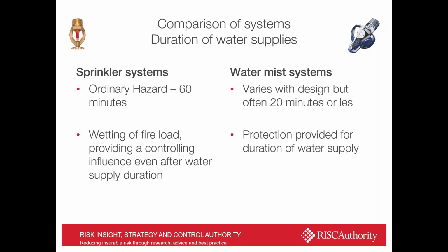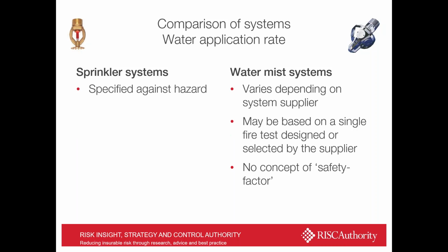In water mist systems, the durations are generally very much smaller. They may be defined by a standard, but often by the installer themselves or the manufacturer themselves, determined through testing. But obviously, in putting so little water down, once the system generally finishes firing, there can be little residual protection of that space thereafter if nothing else has come along to intervene. And then finally, water application rate. We've got it specified against hazard for a sprinkler system, and I think, as I've already described, it's really dependent on the system itself for water mist, as a few equivalent type test procedures apply.